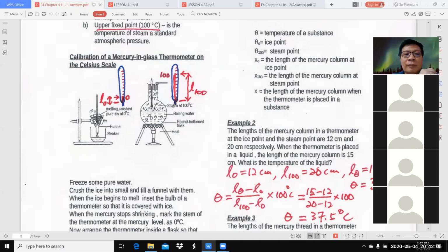That means now, every single thermometer produced in the factory must go through calibration individually, one and all. Cannot say one batch of thermometers do the same. No, they have to do one by one. Calibration has to be carried out one by one.